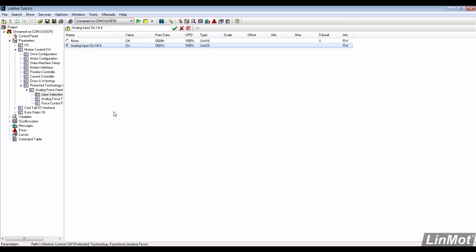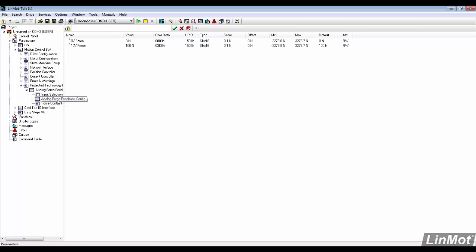Next, we set the 0 and 10 volt values. 50 pounds converts to about 222 Newtons. We set the 0 volt value to negative 222 and the 10 volt to positive 222.